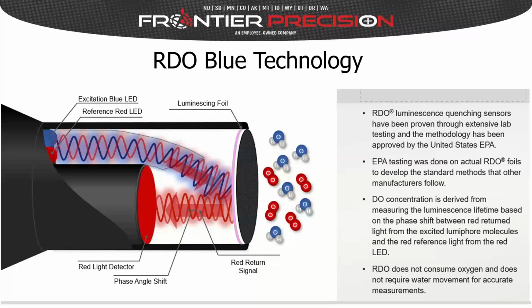Previous to the use of luminescing or optical DO technology, the most common dissolved oxygen sensor technology was called a Clark cell or a polarographic sensor. With this, you had an anode and a cathode at the top of the sensor. There was some electrolyte solution in there, held in place by a porous Teflon membrane that was stretched over the sensor, typically with a rubber O-ring.